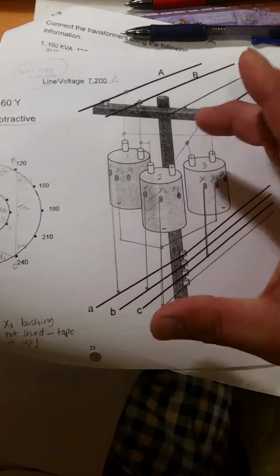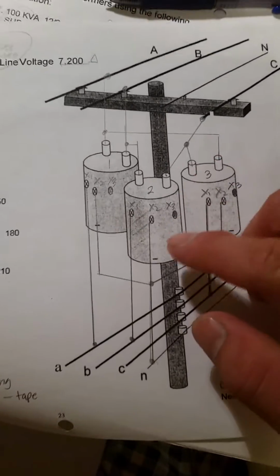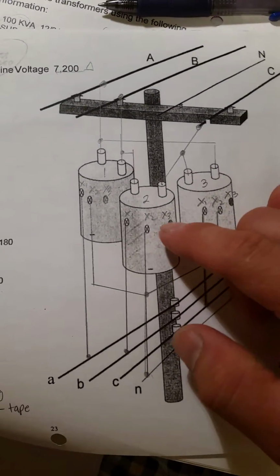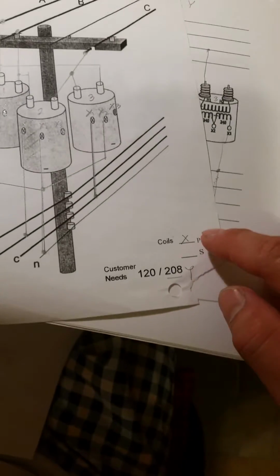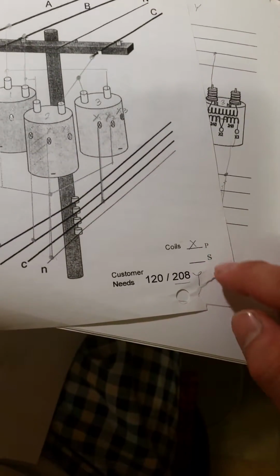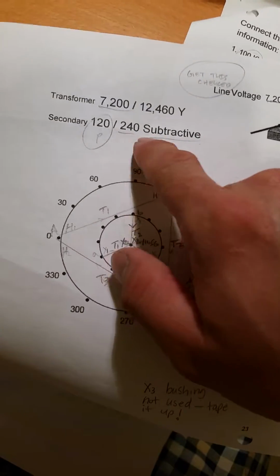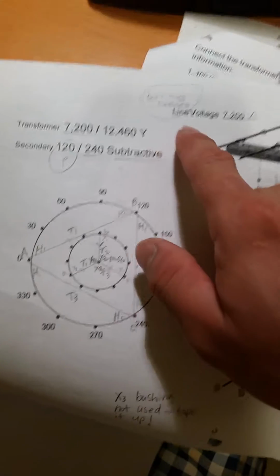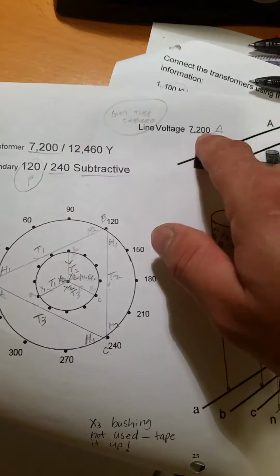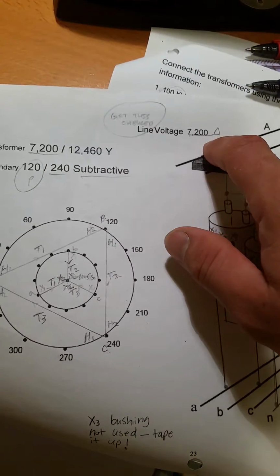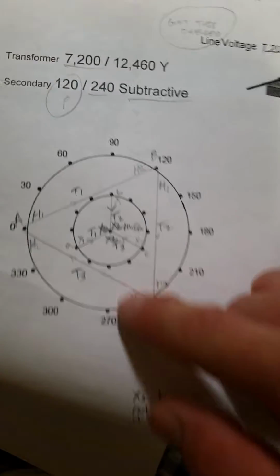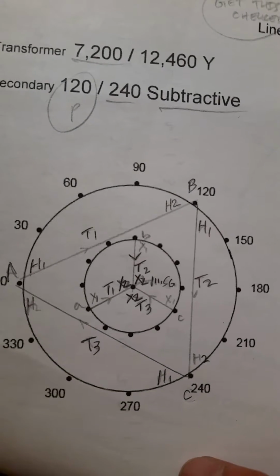And then this one is kind of more of a realistic picture - it's gonna be parallel, so you gotta mark that the coils are parallel. The customer needs 208, but this can is rated for that, so you're going to parallel the can. Your primary voltage is 7200, so they're the same - look at the first numbers, they're the same, so it's delta. And then this is how I did my vectoring for that one.